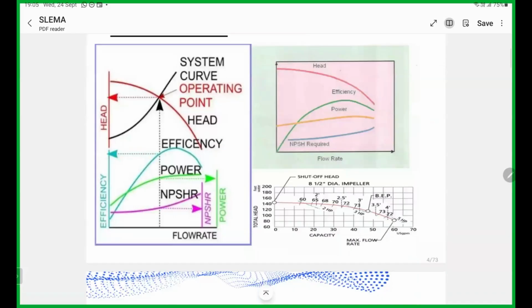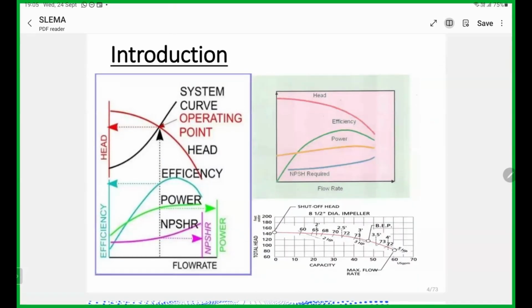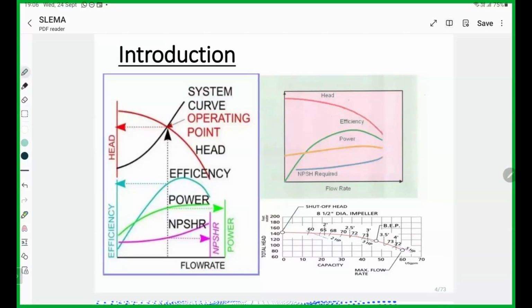If you come to the introduction of the centrifugal pumping system, I am just going to describe the centrifugal pump. We have this pump curve, right? A very important one, and I think most of you know about the pump curve. We have flow rate on this side, Q, and then head, meaning the pressure that the pump can deliver. Head and pressure are the same, but head we generally measure in meters, while pressure is in Pascal or bar or whatever it is. But for centrifugal pumping systems, we use this term, meter head. Then this is the pump curve. Then we have the system curve, and we have the operating point, right? Then this one is very important that you can see here. This is the efficiency curve.